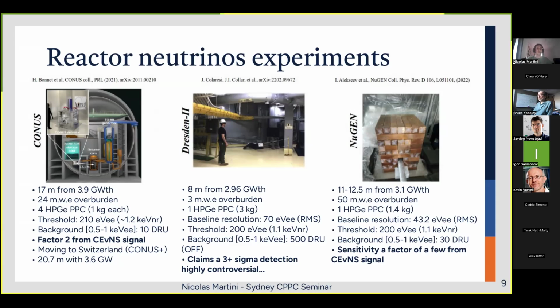And one common point between all of these experiments is the detector that they're using. They're using HPGe PPC, P-type point contact high purity germanium detectors, which are ionization reading detectors trying to measure the ionization deposited in the crystal by the CEvNS events. And these detectors are operated at around 70 kelvins.